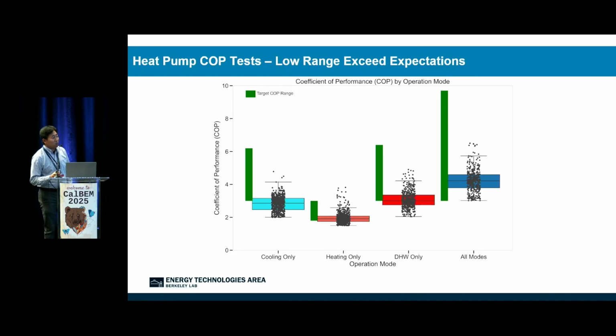All right, regarding the performance of this CO2 heat pump, over the 12 weeks testing period, this heat pump reached the low range of the target performance. For the cooling only mode, the test COP of the heat pump ranged from 2 to 4, and 1.8 to 2.3 for the heating mode, and for domestic hot water, it's about 2 to 4 of the COP. I need to point out the unique feature, which is the high COP of the simultaneous mode.